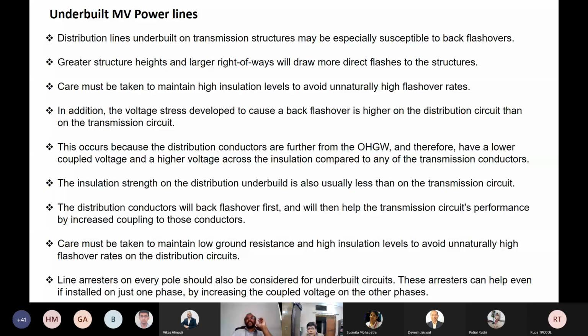The simple reason is that in these areas, when you have a transmission line, it is much taller than a distribution line. So the chances of lightning getting attached to that will be higher, so that the chances of lightning current flowing to the earthing system of these areas is higher than in normal distribution systems. Now the problem is, if the TFR is high, usually the earthing systems are either directly interconnected or coupled to the soil, so that the total potential of the distribution line or distribution tower will also be increased in the event of lightning strikes, so that the chances of backflashover is higher.